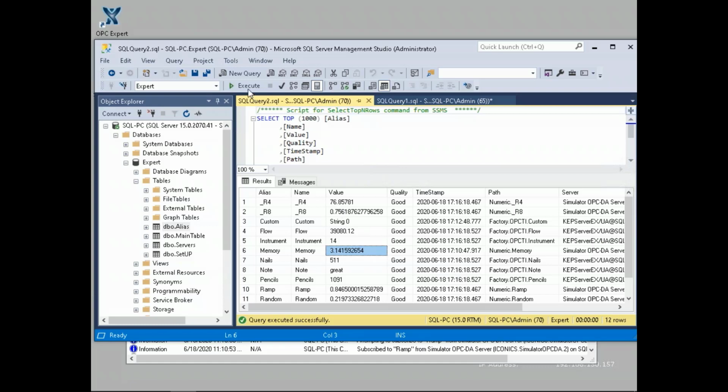So right now it's way after that. If I execute this again, remember, it still hasn't changed. So no, this does not change, right? Now, if the OPC server tells us, hey, wait a minute, I've got a new timestamp, then of course that'll be reflected here, because that's a change by the OPC server. But otherwise, even if you're in disconnected mode, as long as the timestamp doesn't change, it might go to bad and then go back to good again. So this is done as you would expect it, Chris.